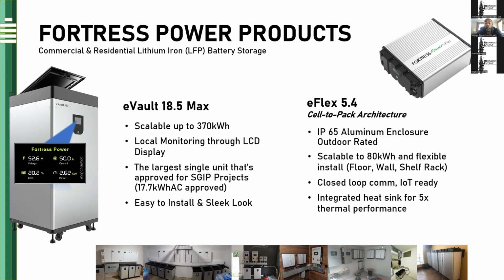When you take a 48 volt residential battery, you get the ability to go into 208, 120, or 240 volt solutions, which we find in residential homes. When you go into a true three-phase solution, you take a single phase inverter and put three of them together, basically putting an inverter on each phase of the system.